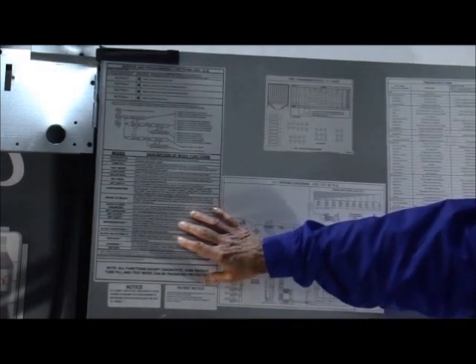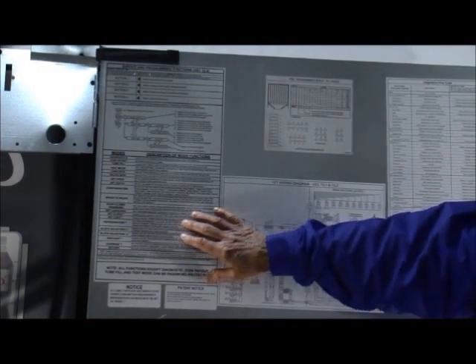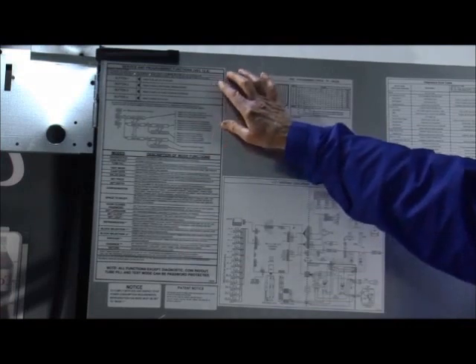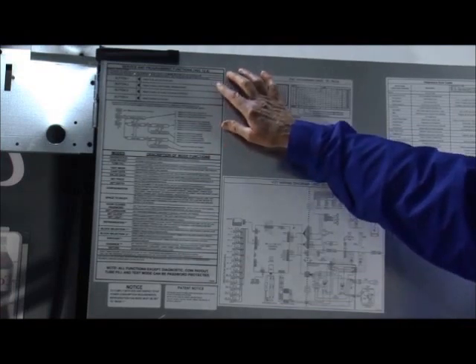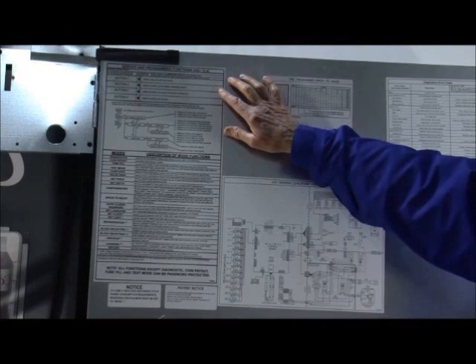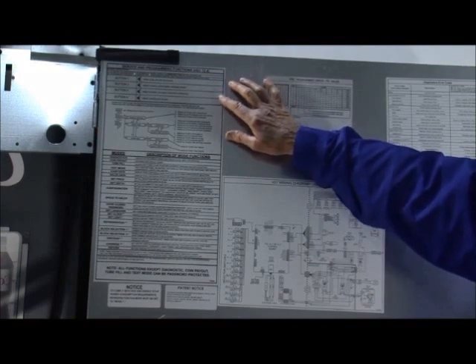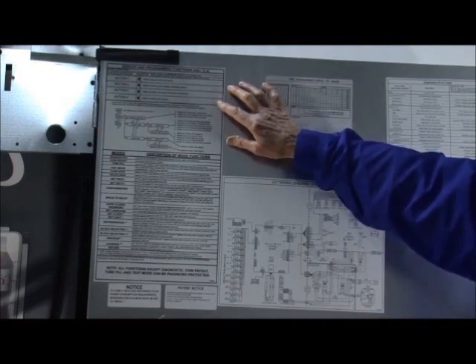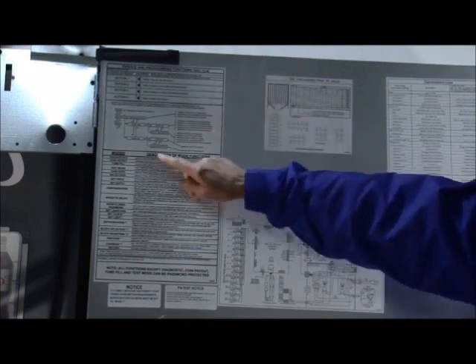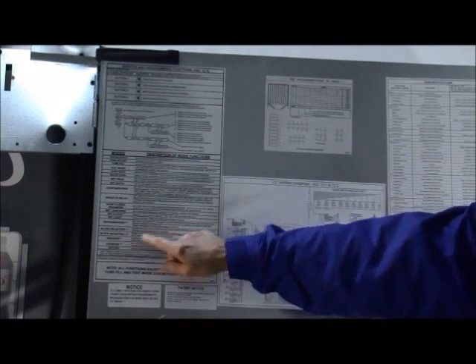On the inner door, we have several decals. This decal here is your service and programming functions. It shows you that it is standard 4-button programming. Button 1 is your escape button. Button 2 will scroll you down. Button 3 scrolls you back up. 4 is your enter and save button. Shows you all your modes on the main menu and all your sub modes that you can enter into.